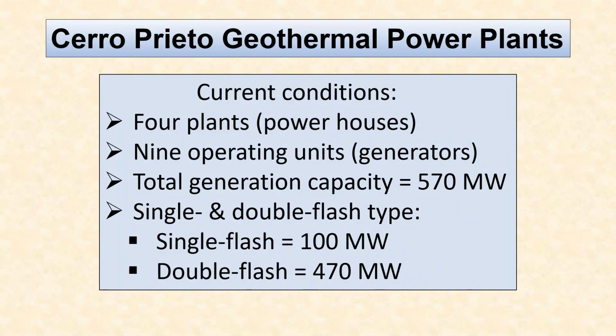Okay, this is the current situation. We have 4 power plants. I define a plant as a powerhouse. Within those powerhouses, there are 9 operating units. Every unit corresponds to a generator. And as Luis pointed out, total generation capacity is 570 megawatts. They are distributed between single and double flash type plants, with 100 megawatts in single flash and 470 megawatts in double flash. And to date, there has never been a binary power plant in operation at Cerro Prieto. Next slide.